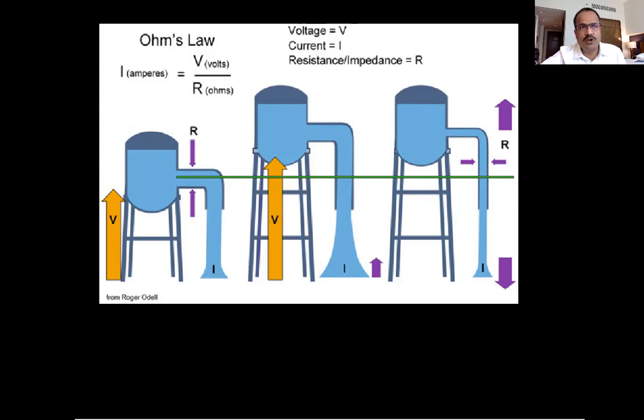This typically we find in operation theaters when the effect is not happening, the doctor tells the assistant, increase. Now that poor fellow does not know what to increase. He comes back and the doctor does not like to be questioned. He says, what to increase? Doctor says, okay, increase the current. Then he goes and checks on the machine. There is nowhere it is written current. So we have to understand, by increasing voltage, the current increases. This is Ohm's law, where current is voltage upon resistance of the tissue. Okay. So by increasing the voltage, you will increase the current.